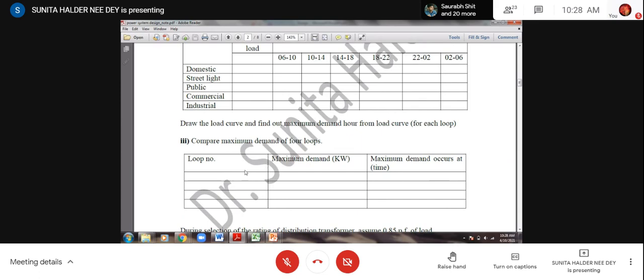So in each sub block there will be a maximum demand. Maximum demand means the summation of demand where it will be maximum, that is maximum demand. So you can fill up this one, these four for 4 sub blocks. Then you can identify from the table also where maximum demand is occurring. So ideally, this time span will be the same for each sub block. For your case, it will come the same because your residential loads are always prevailing, but you must check that one. Understood my point?